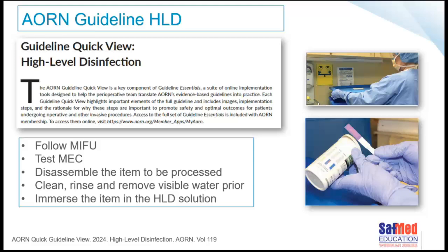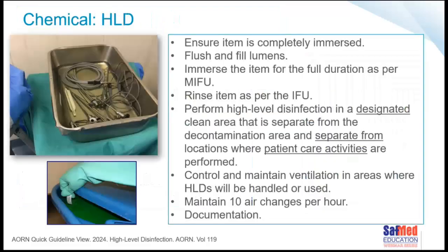Disassembling the item properly, making sure there's proper contact, cleaning, rinsing, removing visible water. Remember, if there's too much water, if there's debris left on the device, we're never going to disinfect it properly, and too much water is just going to dilute the high-level disinfectant. And of course, immersing, which we've spoken about, completely submerging so that there is full contact. Flushing and filling the lumens. Immersing and making sure that the contact is for the full duration as per the manufacturer's instructions for use.